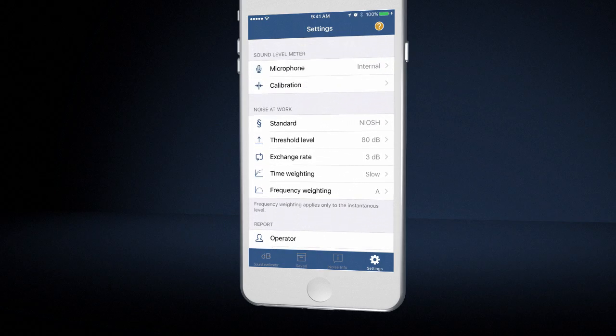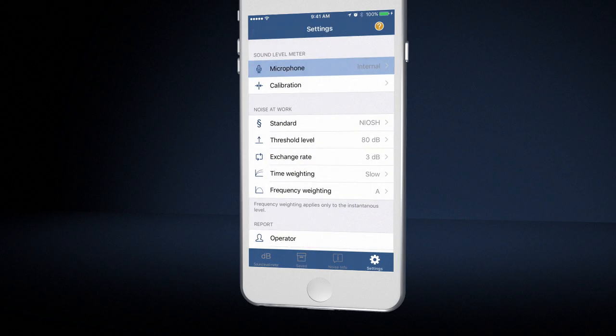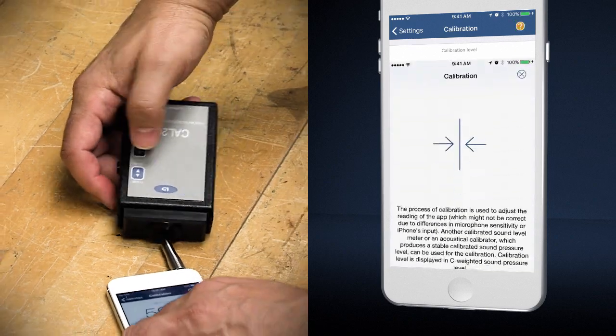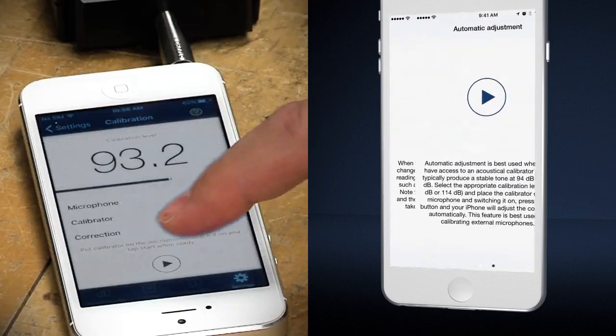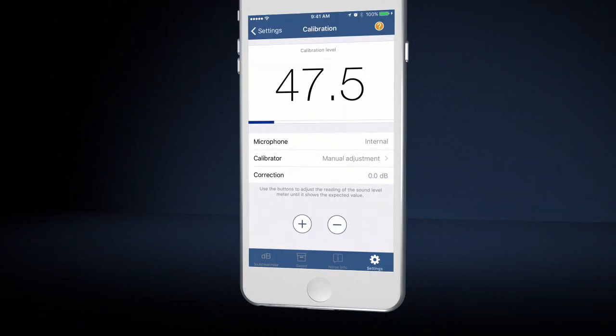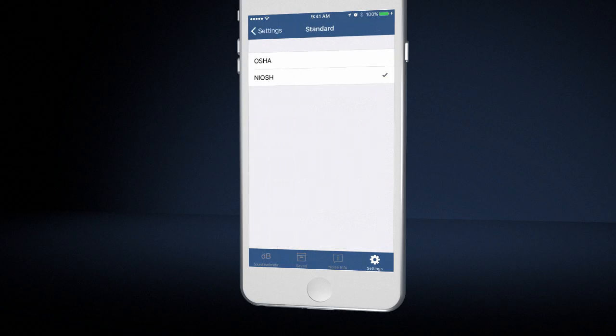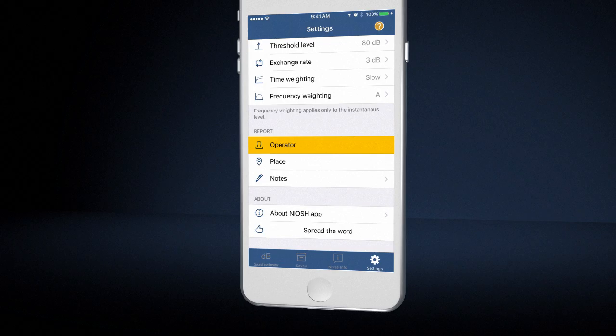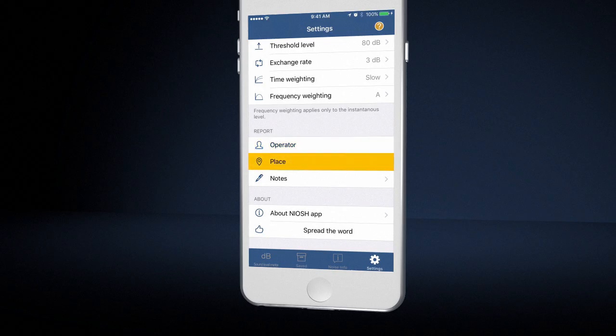For instance, under Microphone, you can select between the internal and an external microphone. Under Calibration, you can calibrate the sound level to a known sound source such as an acoustical calibrator. There are three help screens that can guide the user in conducting an accurate calibration. The app's default is to make measurements based on the NIOSH REL, but it also allows measurements based on the OSHA permissible exposure limit. The app allows the user to set threshold level, exchange rate, time, and frequency weighting. Under Report, the user can enter the operator name, location manually or automatically using the GPS location icon, and any additional notes up to 500 characters.